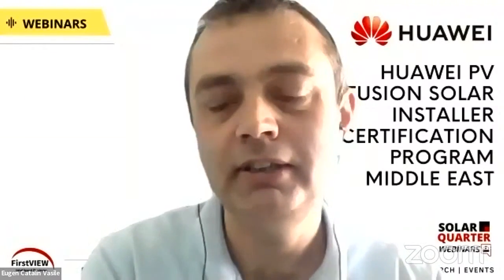Yes, this is another story here. What I can say is this: do not exceed the voltage recommended by Huawei and the short circuit current. This is mandatory. And second, use a tool to design your string. In your area, maybe you don't have so many problems with low temperature, but here in Europe, we have winter and a lot of problems with the string design.